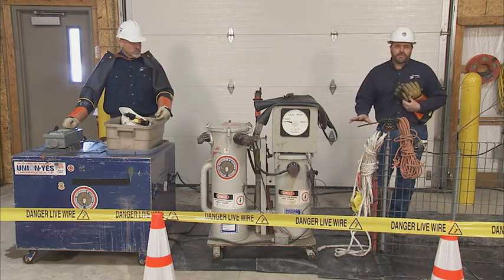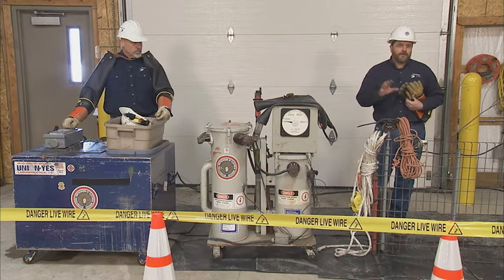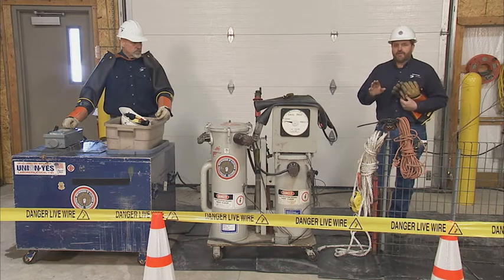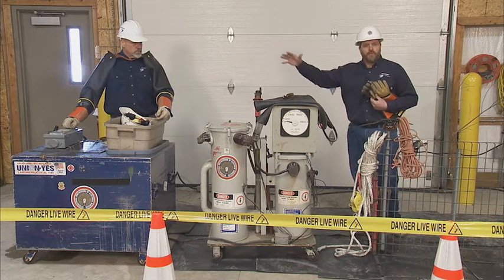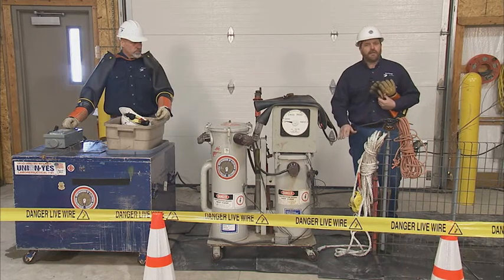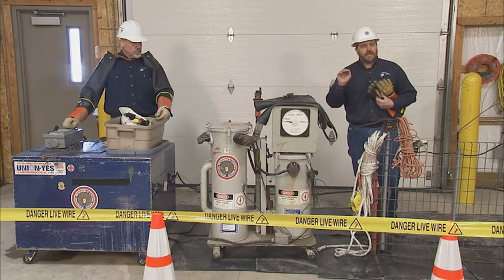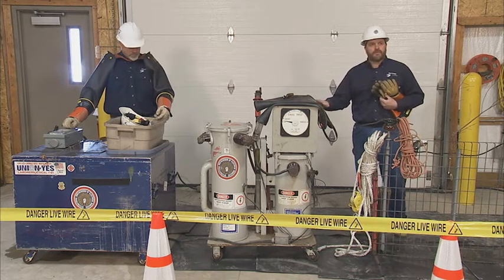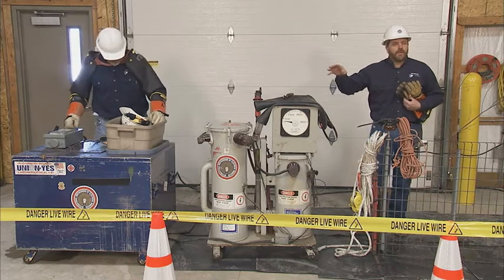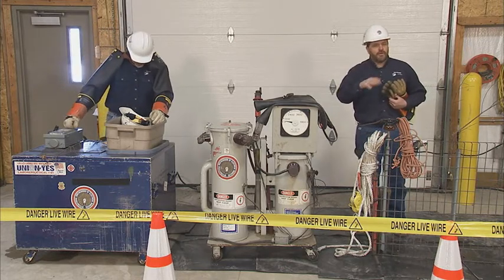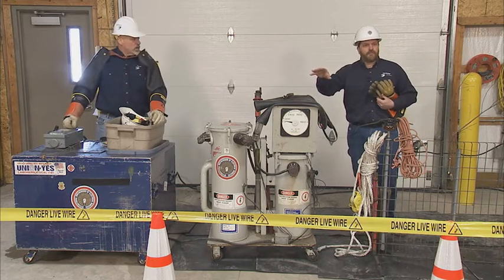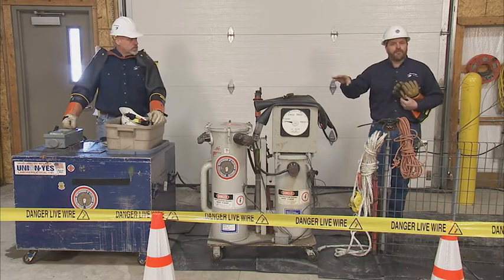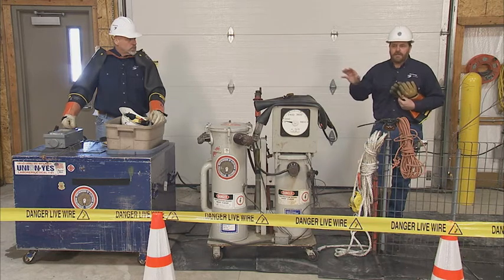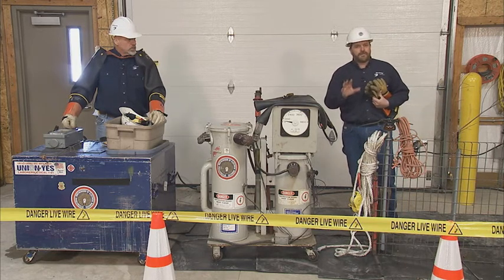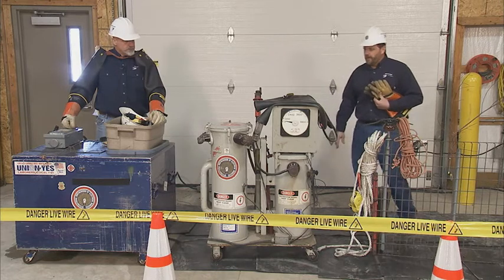In a wire down situation, whether it's primary or secondary, if things are still intact and going to the transformer, if a customer fires up a generator out there, that generator could produce the same type of voltage that we normally do on a primary side. They could take that 120, 240 volts, take it out their overhead service and find this overhead transformer and produce that same high voltage. Also, if they have an underground service, they could go out and find that first green transformer sitting in their backyards and produce that high voltage and get back to our overhead lines. It poses a great problem not only for us as employees but also for the public out there too.